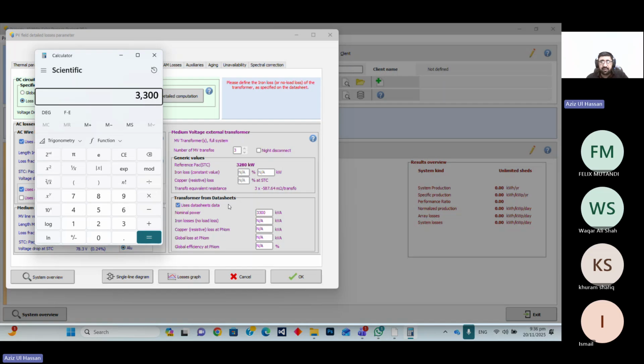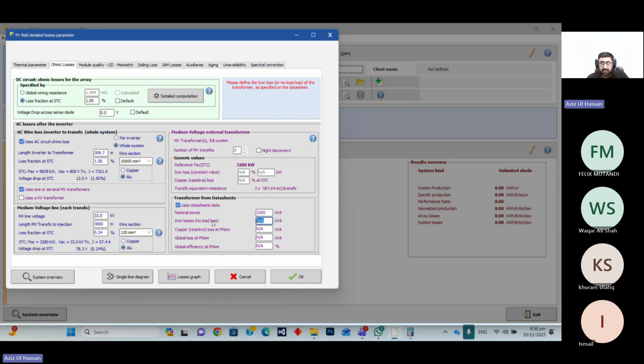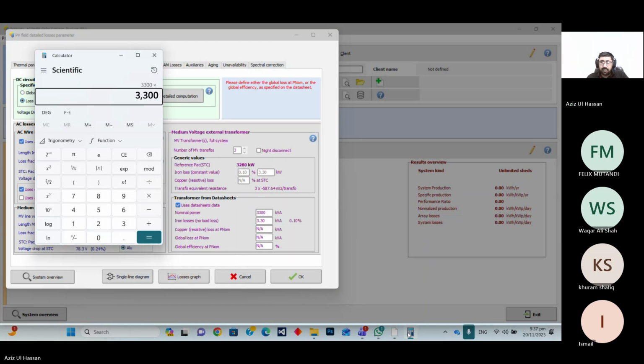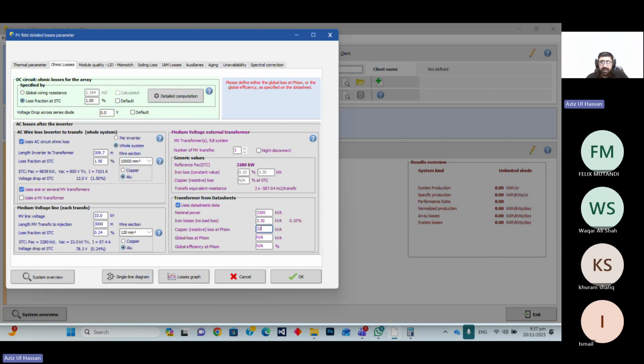So we have a 3300 kVA system and we have to take 0.1%, divided by 100, so 3.3 kVA is the iron loss available. And for the 1% copper loss, 33 kVA divided by 100, sorry, copper losses. So these are not fixed values. We have to check, and as per our experience, most of the cables and most of the transformers have these types of values. Not higher than this. Mostly it is less than that.